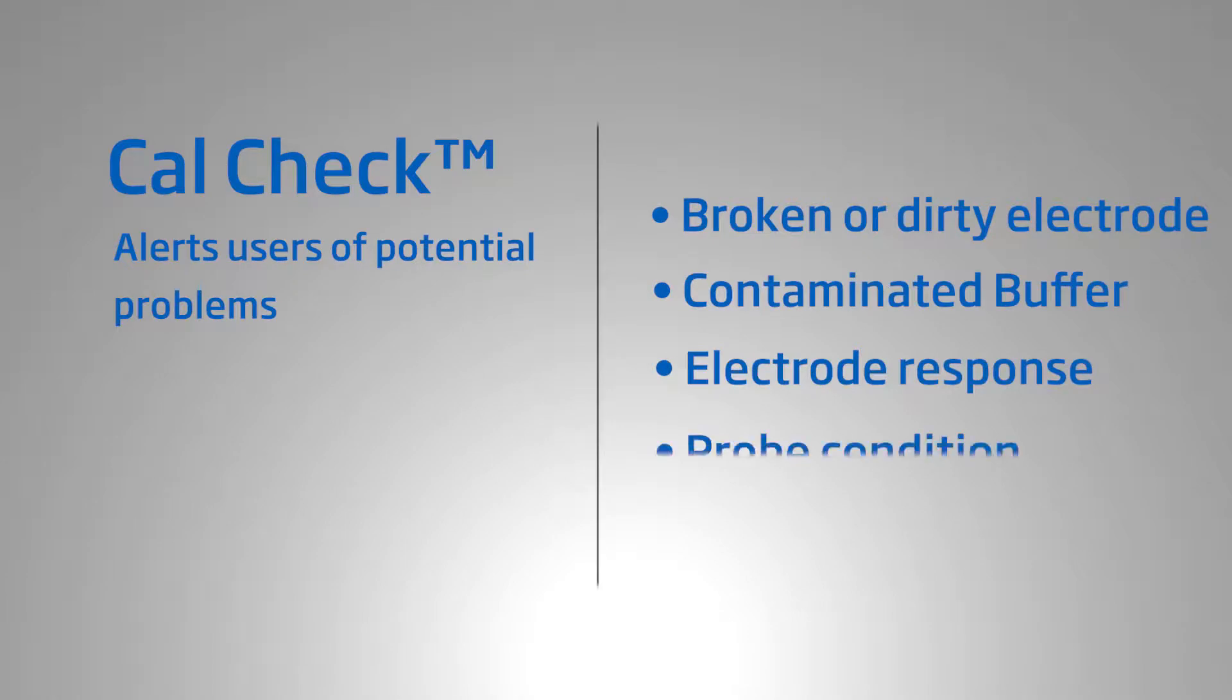A unique feature this meter offers is Hanna's CalCheck. CalCheck alerts users to potential problems during the calibration of the pH electrode like a broken or dirty electrode, contaminated buffer, electrode response time, and the overall probe condition as a percentage that is based on the offset and slope characteristics.